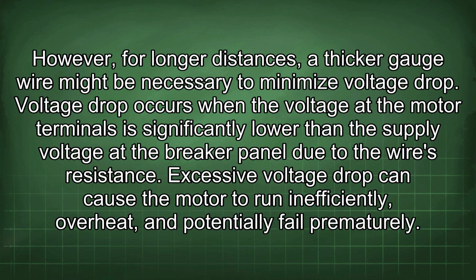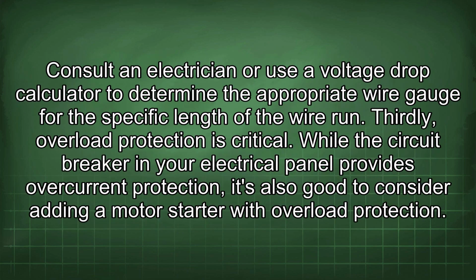Voltage drop occurs when the voltage at the motor terminals is significantly lower than the supply voltage at the breaker panel due to the wire's resistance. Excessive voltage drop can cause the motor to run inefficiently, overheat, and potentially fail prematurely. Consult an electrician or use a voltage drop calculator to determine the appropriate wire gauge for the specific length of the wire run. Thirdly, overload protection is critical.